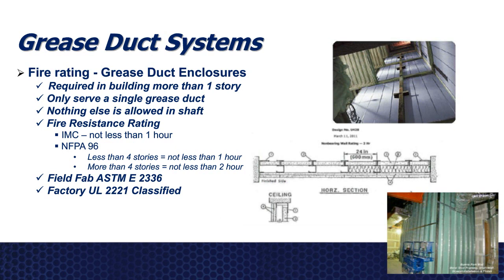Fire-rated shafts: if I have a grease duct that's going to be in a building that is multiple stories, that grease duct needs to be inside of a fire-rated shaft. Again, as I mentioned before, we're trying to protect the fire from spreading from a kitchen area throughout the rest of the building. So in a building that's greater than 1 story, a fire-rated shaft would need to be constructed to have that grease duct in. And that fire-rated shaft can only serve a single grease duct. So if I had a high-rise condo building and I had 4 or 5 different hoods in different areas of the kitchen, and I had to route those to the top of the building, that means I had to have 4 or 5 separate fire-rated shafts to run those grease duct systems in, and then nothing else could be inside that shaft. So you can imagine the amount of space and cost it would be to do that inside of a facility.